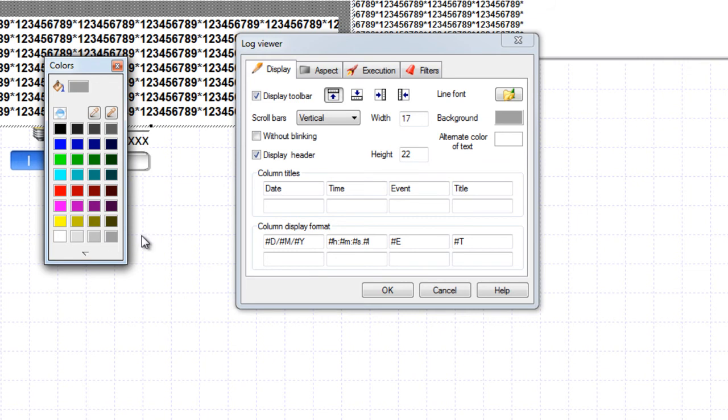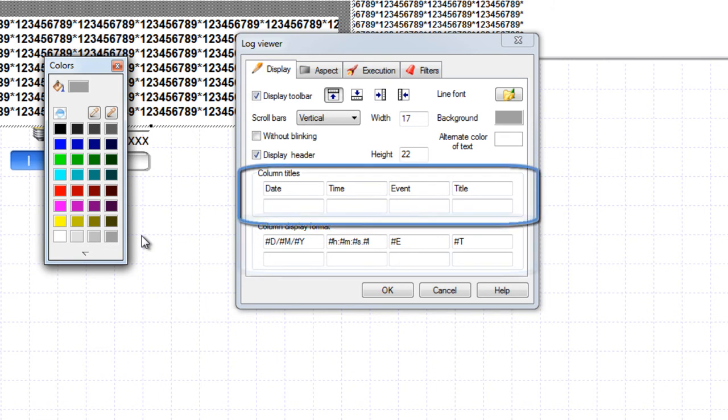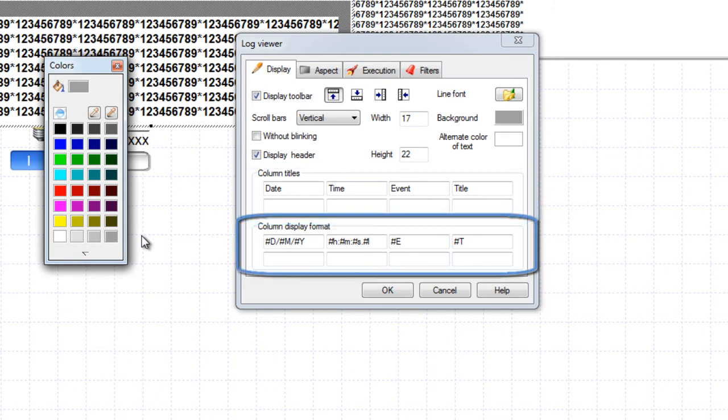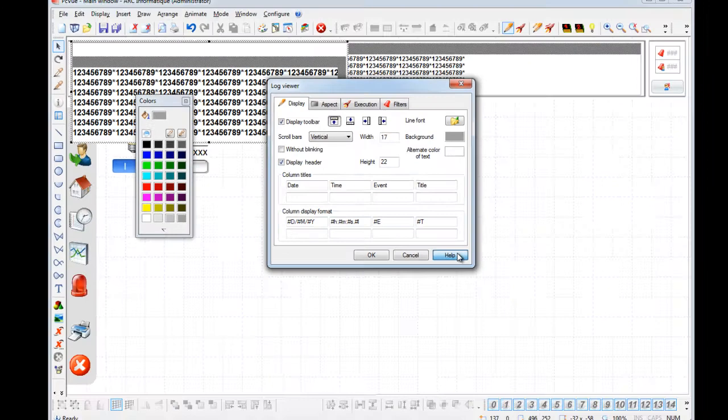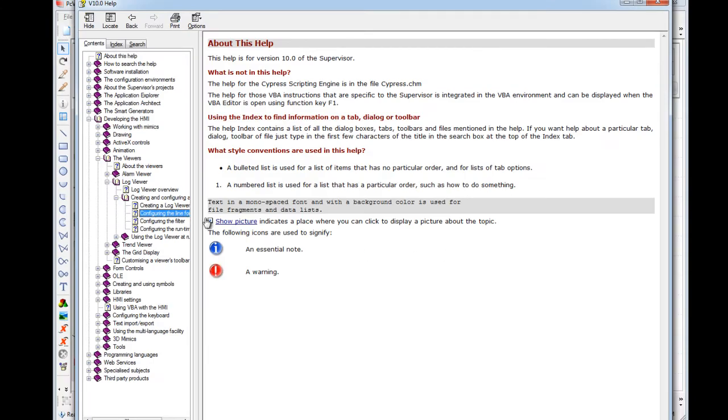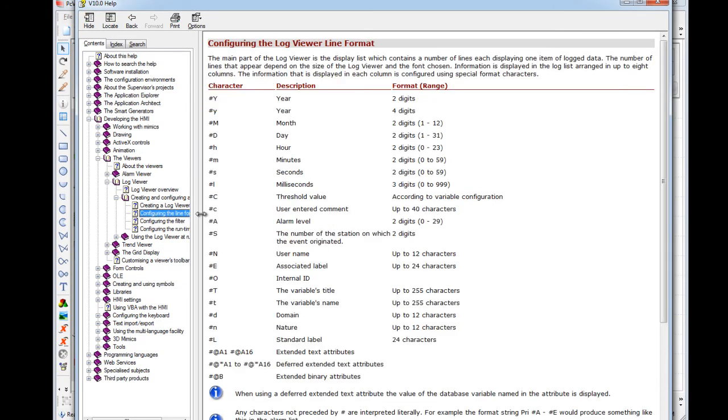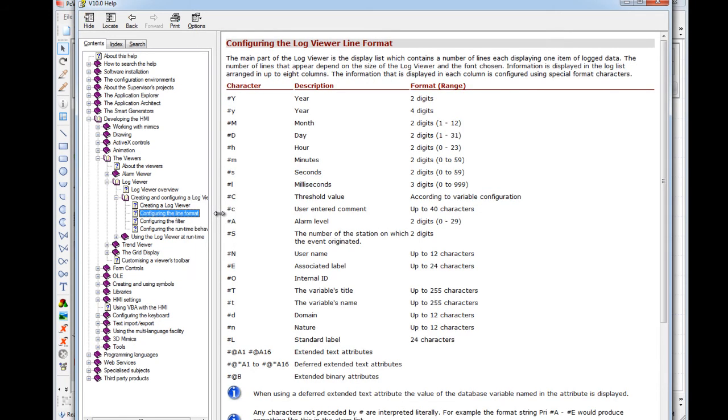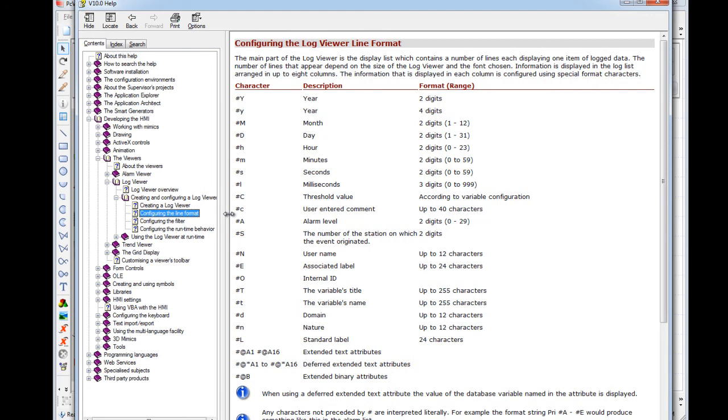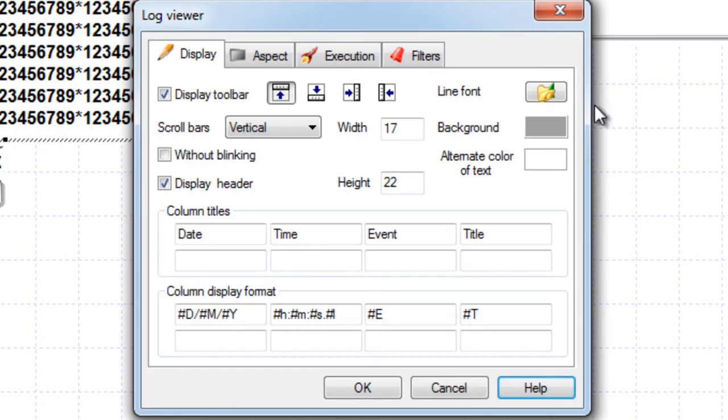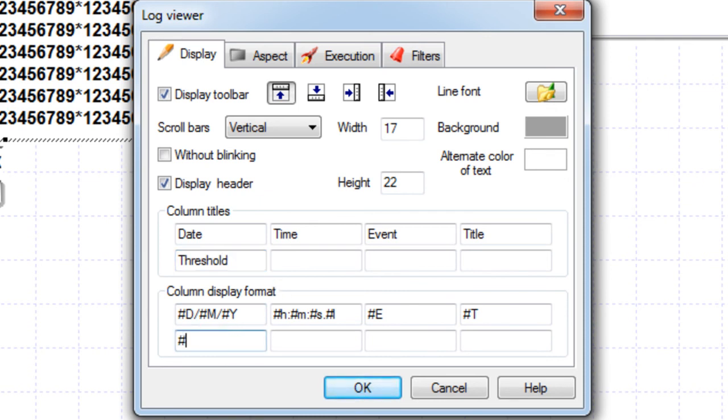The log viewer can display a maximum of eight columns with fully customizable content. You can configure the column title and display format in the corresponding columns using substitution characters. Let's click the help button to access the online help. The topic configuring the log viewer line format shows all the format possibilities. For example we can add a substitution to display the threshold value triggering an alarm. Here we will enter the title for the new column threshold and add the substitution pound C to display the threshold value.